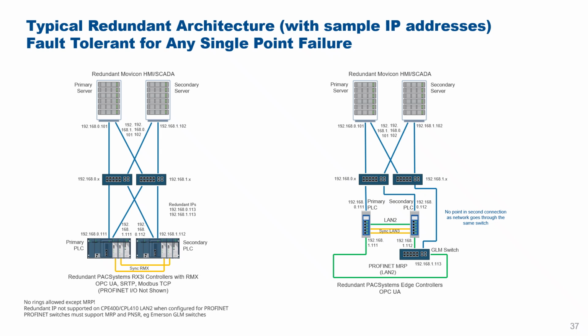And again, this is on a separate subnet, but now what you've got to do is you've got to use that GLM switch in order to connect your backup network to LAN 2 port on the CPE400 or CPL410. Now, you could have two network connections, but there's no point, and also that would potentially create a ring. So what I'm doing here is just a single connection from my secondary Ethernet switch to the GLM switch, and that gives me my backup connection. So yeah, it's a very different architecture, but it gives us the same effective support. But now we do need that additional GLM switch. But certainly if you've got edge controllers and you want to do redundant communications with redundant LANs, it is possible.